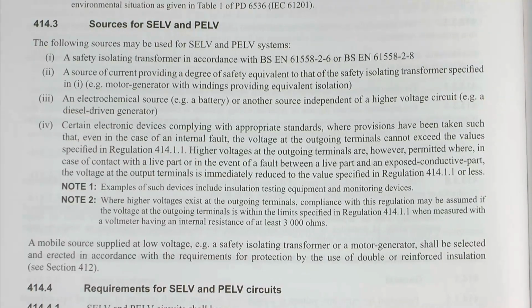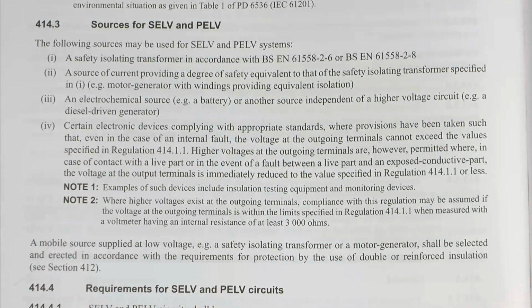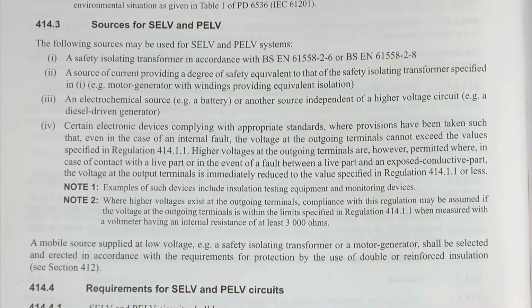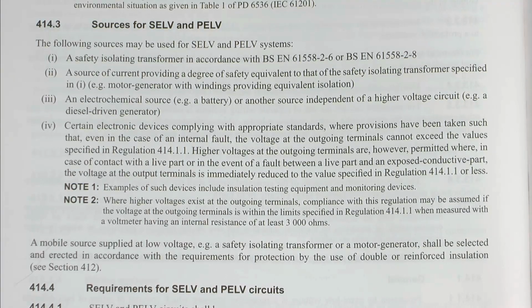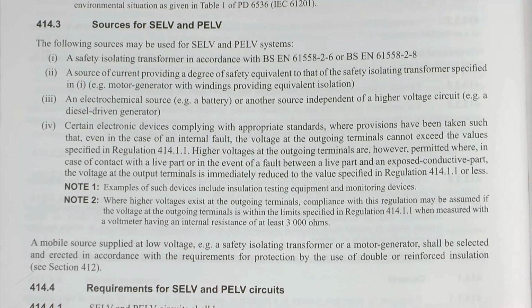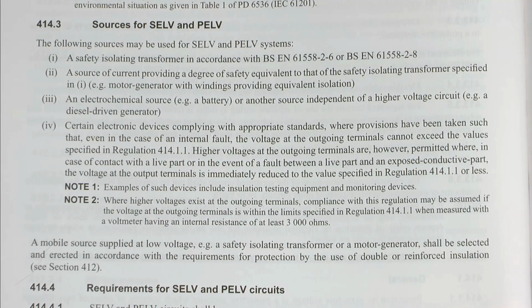So this is the particular piece it's referring to, and it's this piece here in 4. Certain electronic devices complying with appropriate standards, where provisions have been taken such that even in the case of an internal fault, the voltage at the outgoing terminals cannot exceed the values specified in 414.1.1. Higher voltages at the outgoing terminals are, however, permitted where in case of contact with a live part or in the event of a fault between a live part and an exposed conductive part, the voltage at the output terminal is immediately reduced to the value specified above.